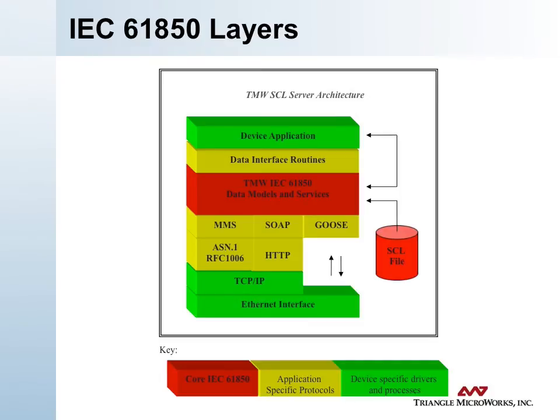The same layered architecture as defined in the reference model is used in the way we build real devices. This diagram shows the triangle server architecture. Device applications, through a set of interface routines, interact with the core 61850 library. This package builds the object models directly from the substation configuration language file, which defines the IED capabilities. These models are then mapped onto various services in the protocol stacks.